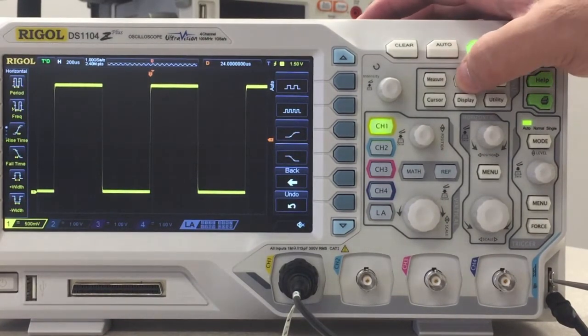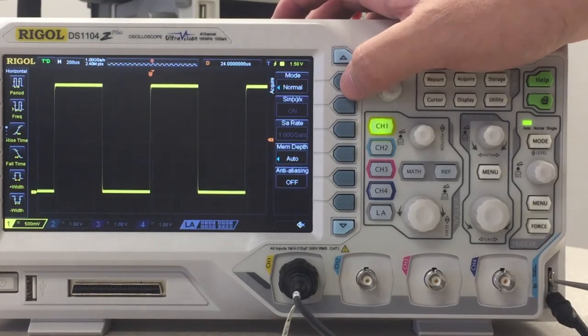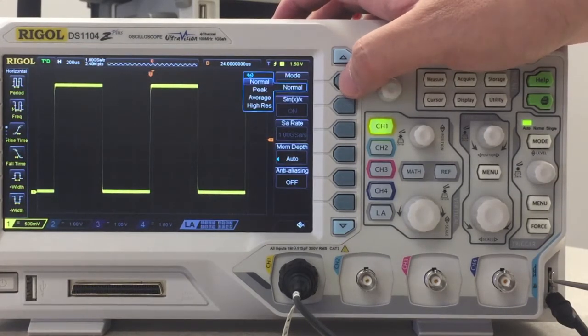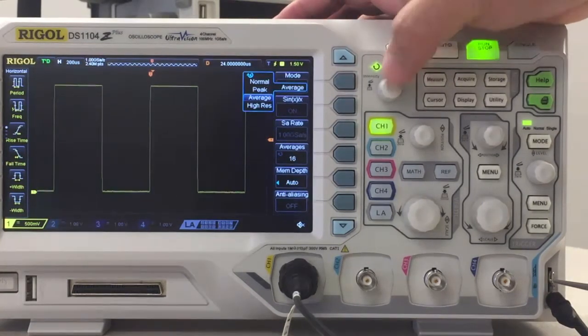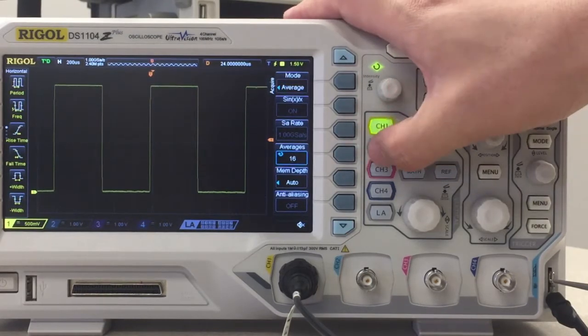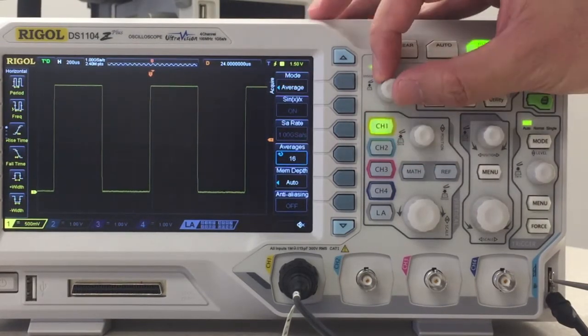Press the acquire key and then press the corresponding soft keys on the right of the display in order to activate the average mode. Turn the intensity knob to adjust the average factor.